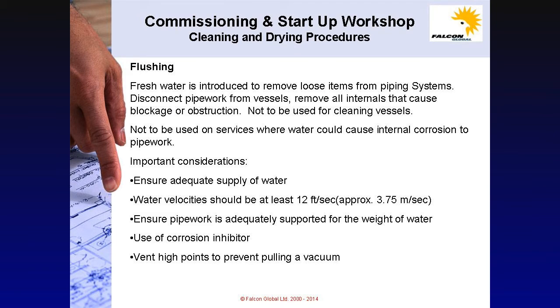Fresh water is introduced to remove loose items from piping systems. The normal procedure is to disconnect the pipework from vessels, removing all internals that could cause blockage or obstruction. It is not to be used for cleaning vessels. It is also not to be used in services where water could cause internal corrosion to pipework. Important considerations are to ensure an adequate supply of water and ensure that the required velocity can be delivered of around about 12 feet per second.